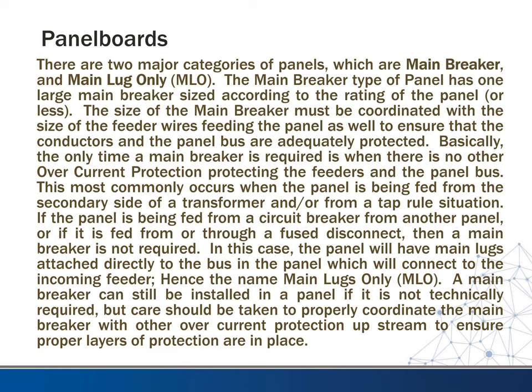So with panel boards, there are two major categories of panels, which are you can have a main breaker board or a main lug only board. The main breaker type of panel has one large main breaker sized according to the rating of the panel, or it could be less than that. The size of the main breaker must be coordinated with the size of the feeder wires feeding the panel, as well as to ensure that the conductors and the panel bus are adequately protected.